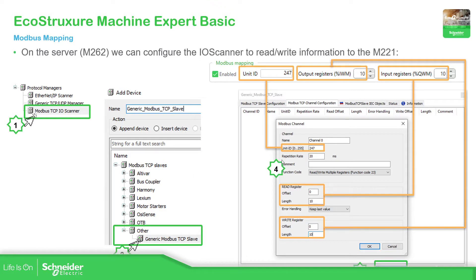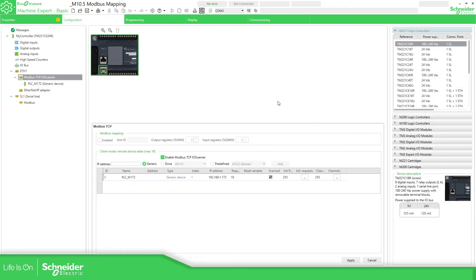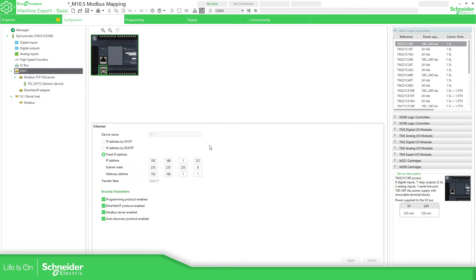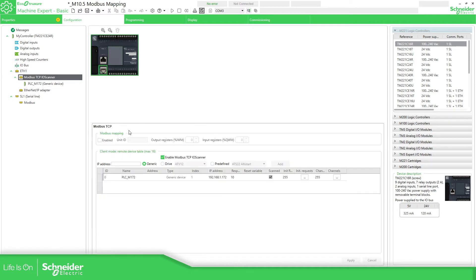Let's go to the Modbus mapping configuration on the M262. This is the same application I've done before. Go to the Ethernet port, configure it to be on the same network, then under Modbus TCP select the unit ID — you can change it, but these are the defaults — and then apply it.